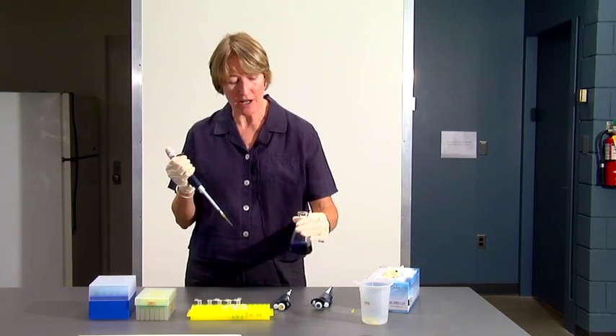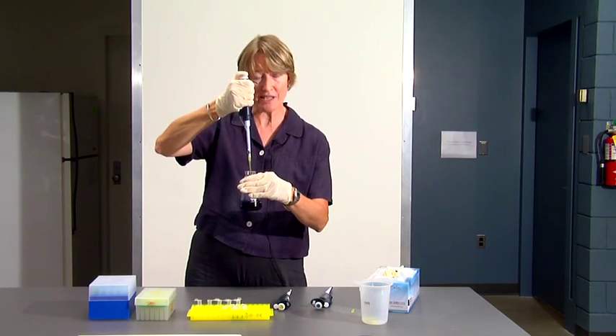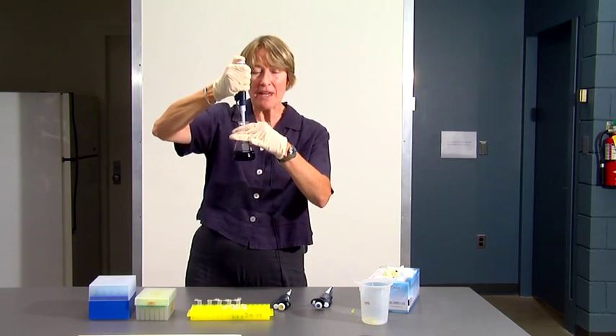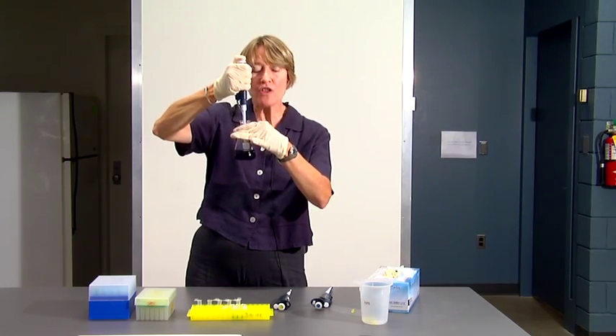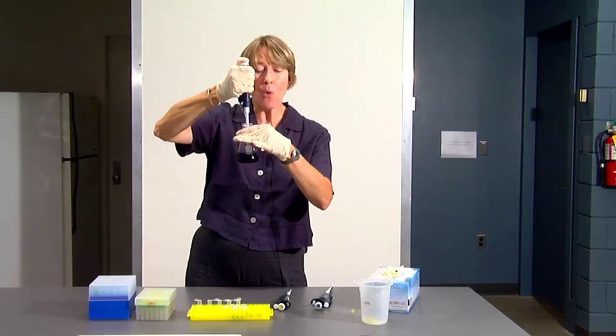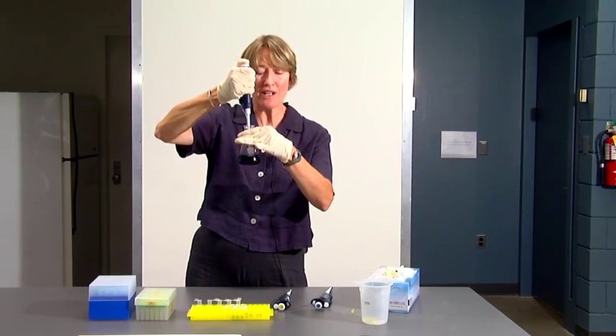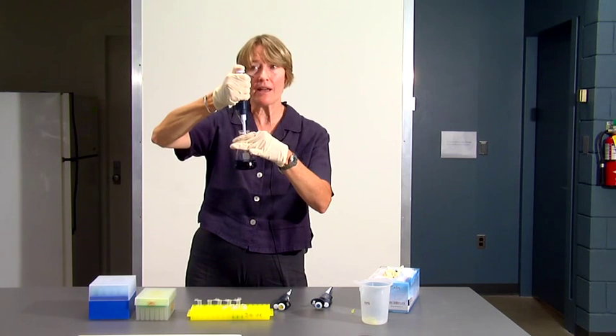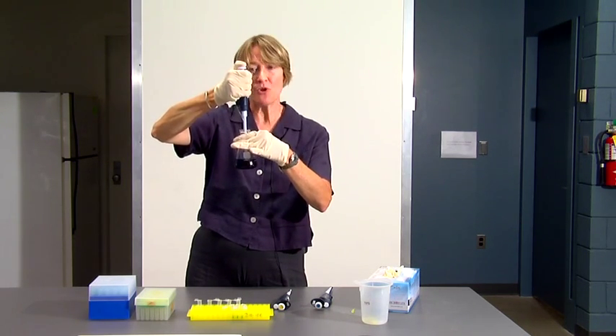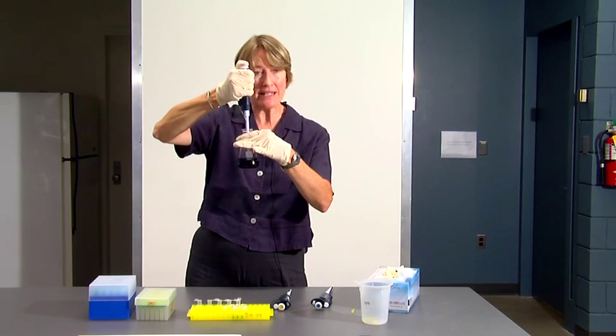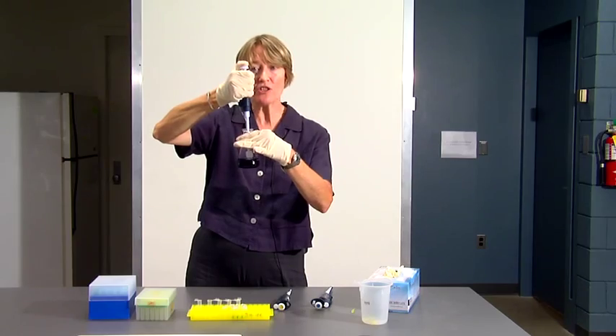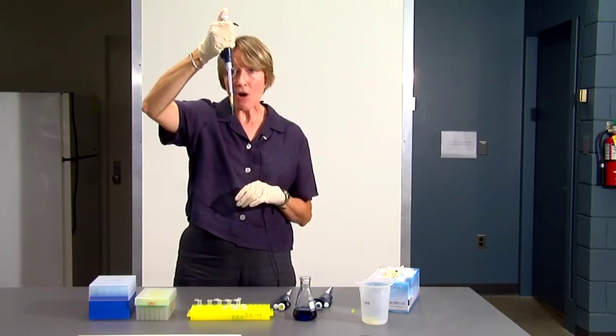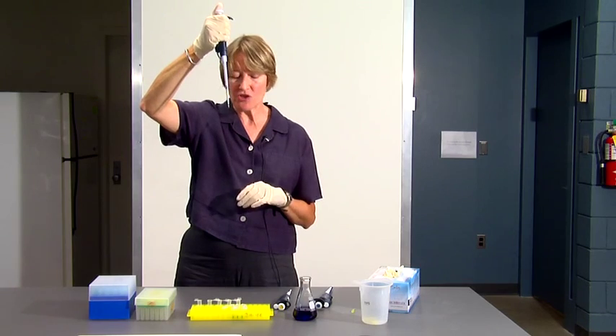So we're going to take some of our sample. You're going to depress the plunger to the first stop. Put the pipette tip into the fluid. And you want to make sure that your tip is below the surface of the fluid, well below the surface of the fluid. You don't want to get the pipetter itself wet. You don't want it to go in too deep. But you want it to go in deep enough so that when you pull up the liquid into the tip, you're not sucking up air. You don't want to get bubbles in the tip. So I pushed the plunger to the first stop. My pipette tip is under the surface of the fluid. I'm now going to slowly release the plunger and pull my sample up into my pipette tip. I now have 100 microliters of accurately measured sample in my pipette tip.